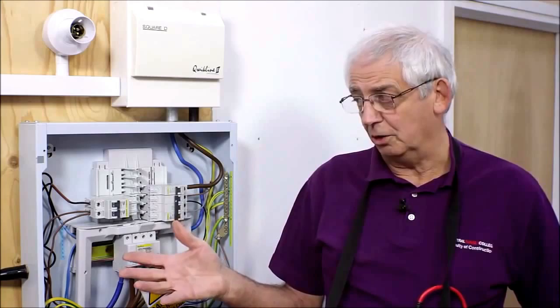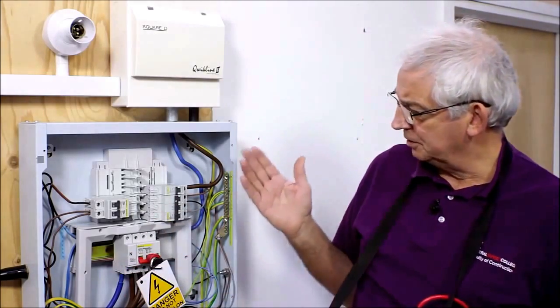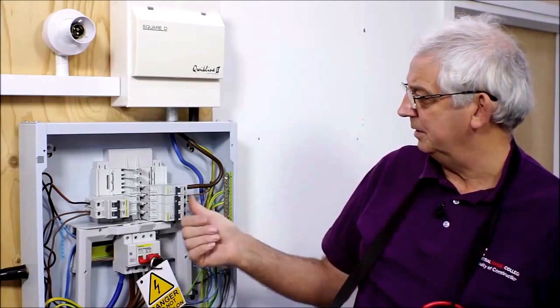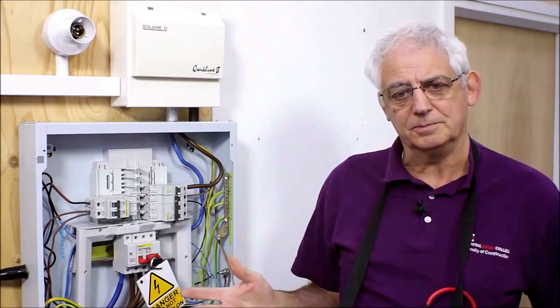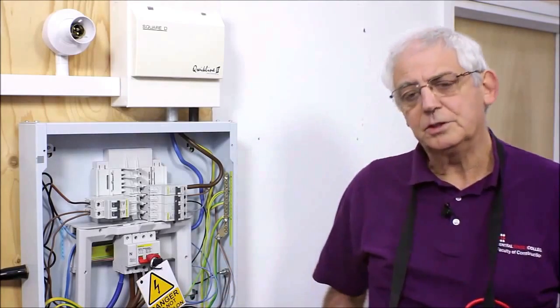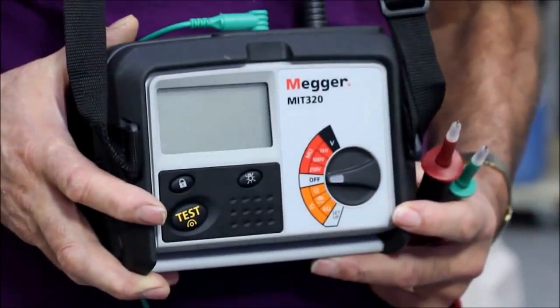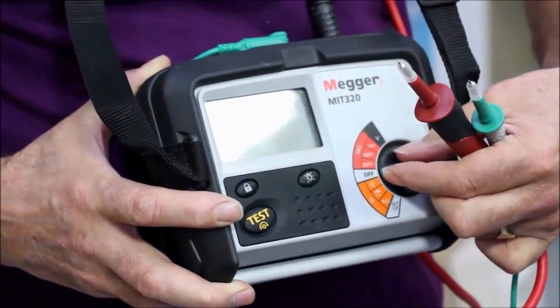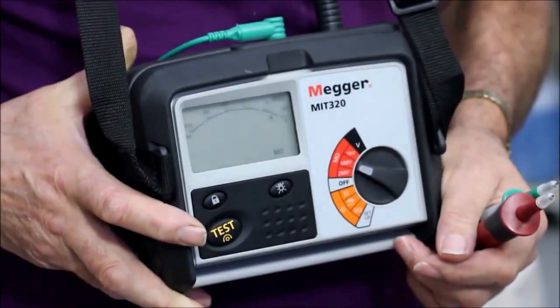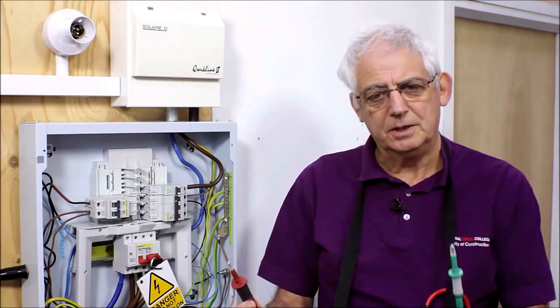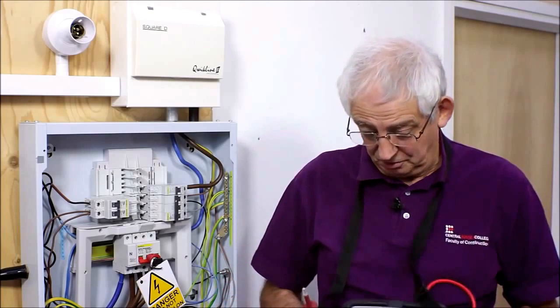So first part of the test, or the first part of the job, is to check that everything is disconnected as should be. As far as the board goes, the board is isolated, but we need to make sure that all of the circuit breakers are on, because we're going to test the complete installation. We're going to use an insulation resistance tester, and we're going to use a test voltage of 500 volts. Because it's a 500 volt test, you have to push the button to liven up the probes.